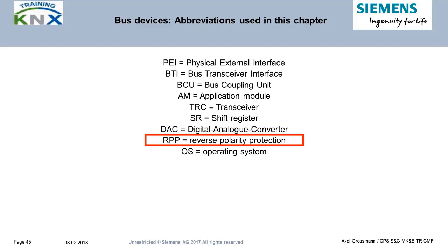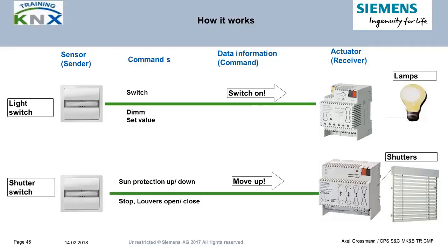The DAC is required if a separate dimming ballast has an analog control voltage input, such as 0–10V DC. RPP is a feature of the TRC chip that prevents the electronics from being damaged if the bus wires plus and minus are mixed up due to reverse polarity. OS stands for Operating System — the core software in a BCU.